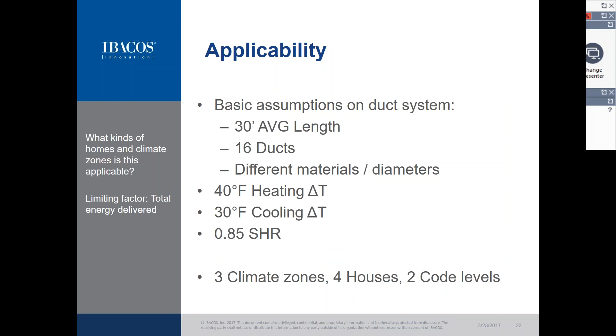Whenever we did the range of applicability testing, looking at the 3-inch flexible ducts, we considered 16 of those ducts at 30 feet average length, and we assumed that we would have 0.35 inches of water, which isn't extraordinarily high. We're not talking about 1 inch or 1.5 inches of external static pressure, but just looking at 0.35 inches, we're estimating that you would get over 1,000 CFM through that 3-inch duct system. That would be enough for a 3-ton air handler without imposing an extremely excessive amount of static pressure and fan energy. So a lot of it comes down to making a much more compact duct layout, so that the total lengths are shorter.